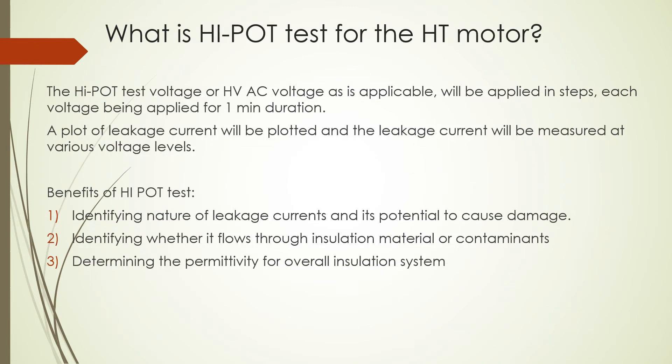The seventh question: what is the hipot test for an HT motor? The hipot (high potential) voltage is applied in steps, each voltage being applied for one minute duration. A plot of leakage current is recorded at various voltage levels. Benefits of hipot testing: identifies the nature of leakage currents and their potential cause of damage, identifies whether current flows through insulation material or contaminants, and determines the permittivity of the overall insulation system.